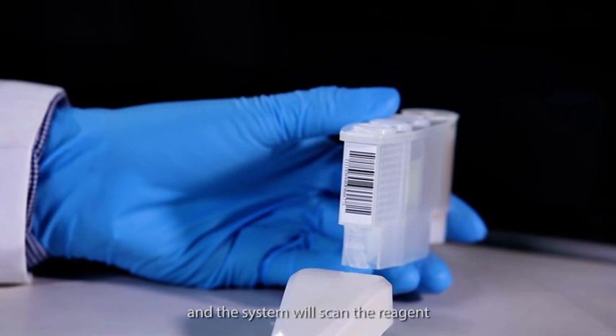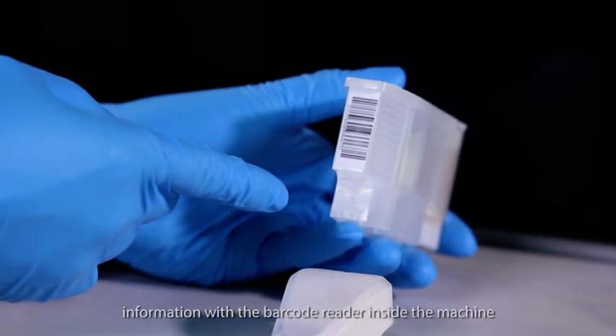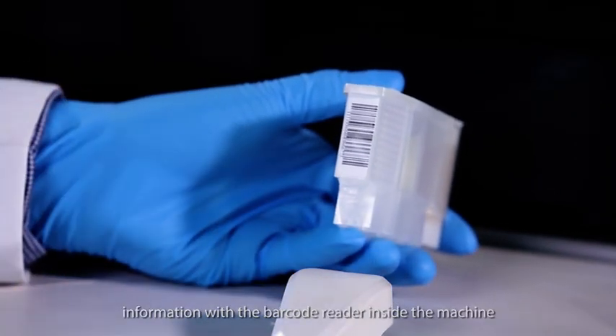In the auto mode, load the reagent directly and the system will scan the reagent information with the barcode reader inside the machine.